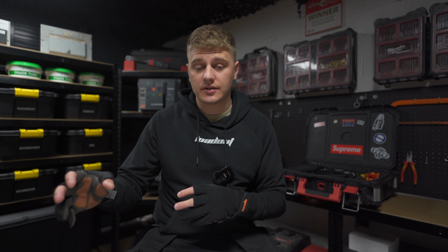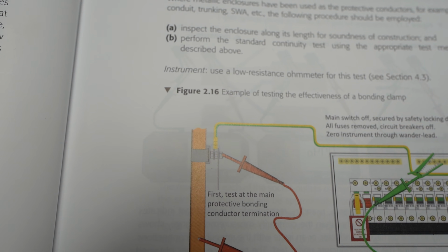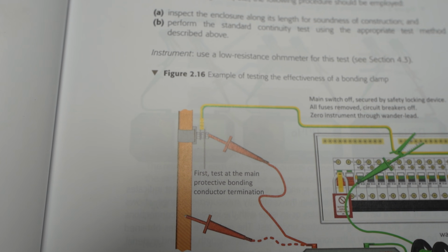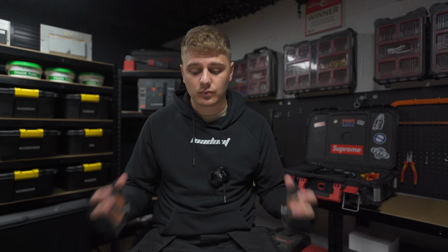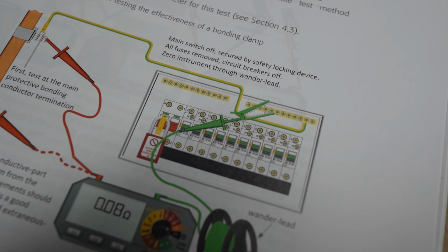So the first regulation I mentioned states the requirement to install equipotential bonding where it's needed, in line with the relevant chapters and other British Standards. And then this second regulation says that we need to carry out a continuity check to verify that it's there and ensure it's going to function as intended. That is why we have the continuity of main protective bonding conductors test. And that's the test that we're going to be running through in this video.